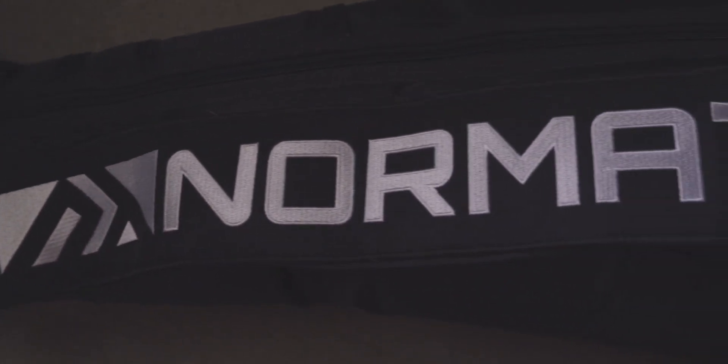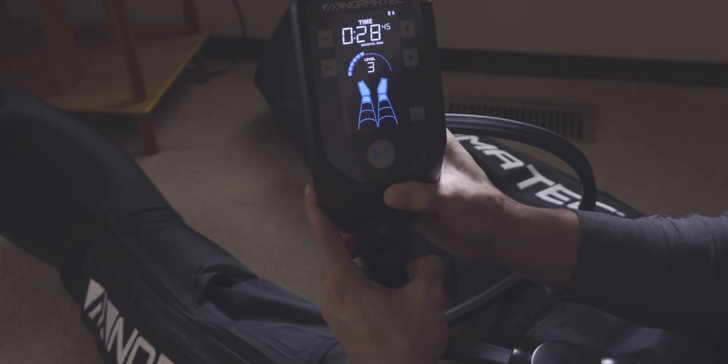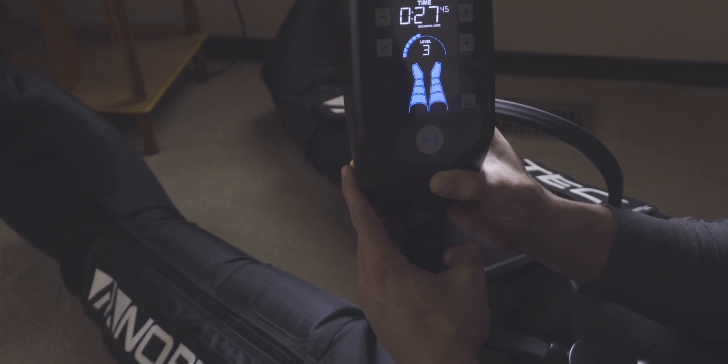As the cells begin to squeeze at varying pressures starting at your toes, it's squeezing up the leg and decongesting the tissues. The different pressures along the leg are also promoting blood flow — it's kind of the same principle as massage: you squeeze, the pressure comes in, moves blood out, pressure releases, new blood comes in. These pneumatic pressure sleeves have been around prior to the NormaTec boots. What made this invention stand out over prior products — or prior art, in legal patent terms — was the varying pressures, or this peristaltic pulse waveform, to promote decongesting of tissues and blood flow. The sleeves can't simply remain at a constant pressure; they need to act in a massage-like fashion, going from minimum to maximum pressures, varying in between and releasing.